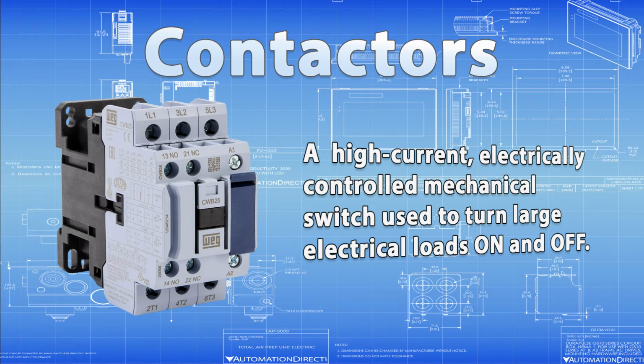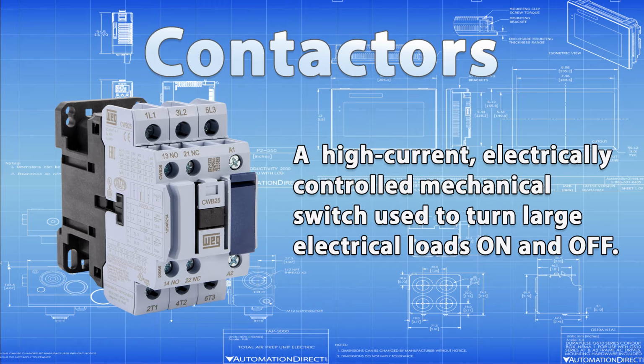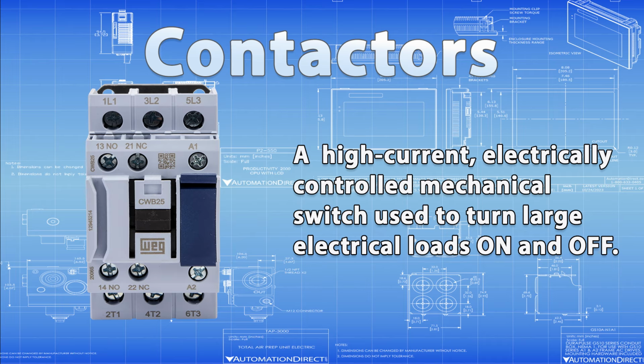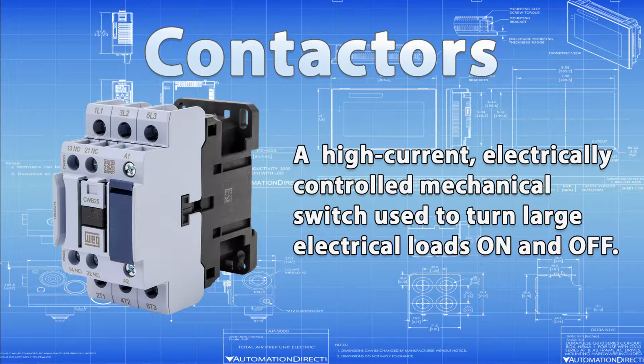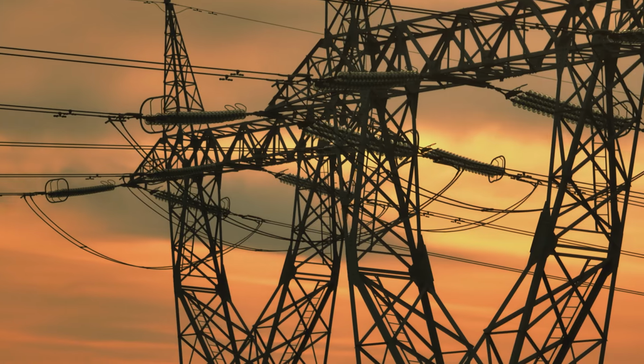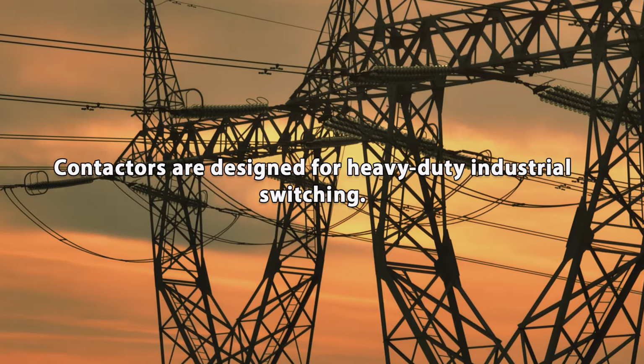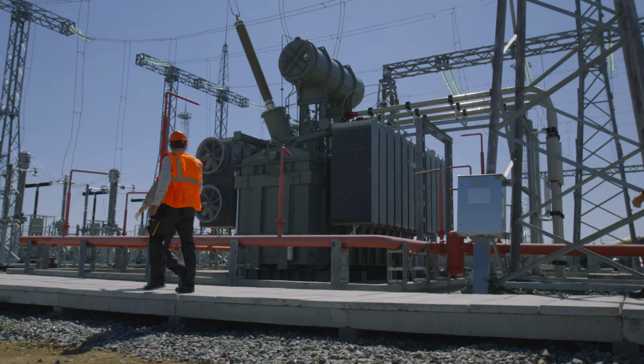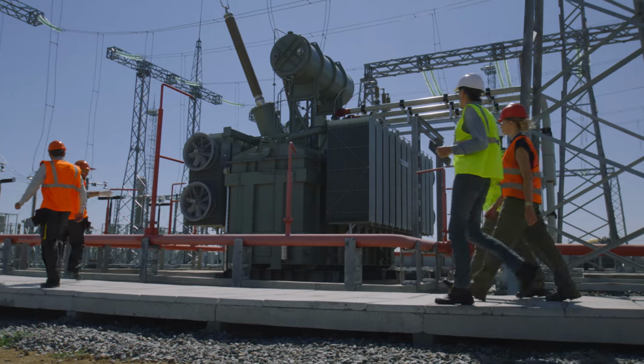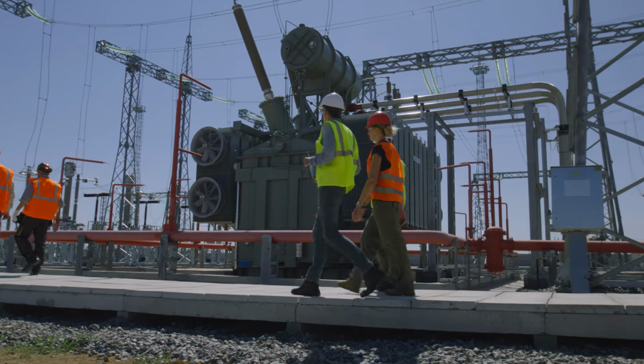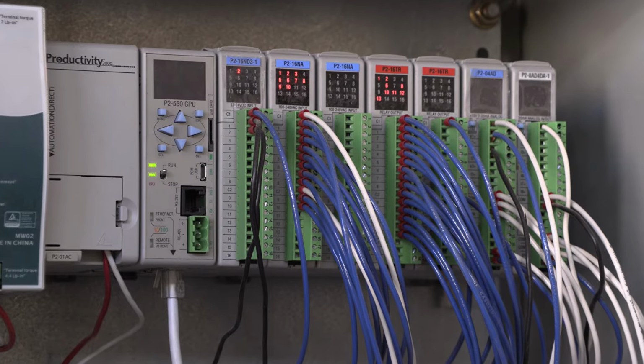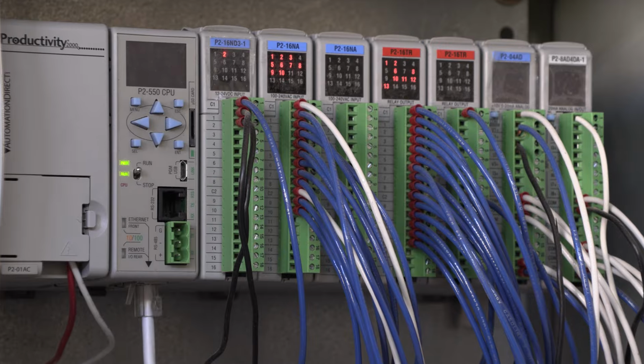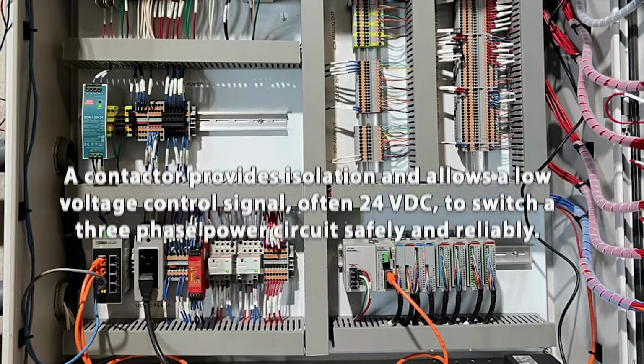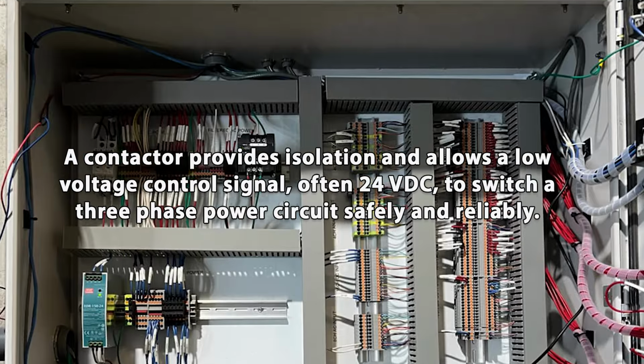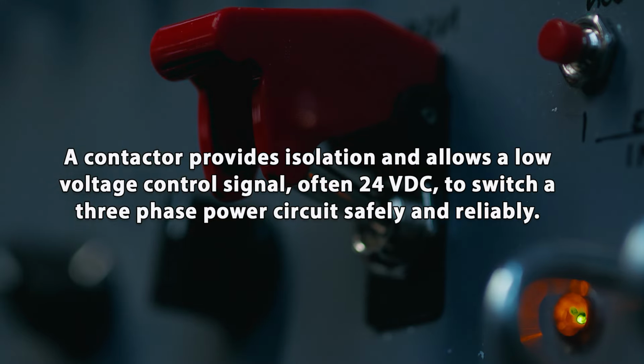A contactor is a high-current electrically controlled mechanical switch used to turn large electrical loads on and off. Unlike standard control relays, which are typically limited to 10 amps or less and often use solid-state internal components, contactors can handle hundreds of amps and are engineered specifically for heavy-duty industrial switching. Industrial motors, solenoids, and transformers generate large inductive electrical loads and voltage spikes. Connecting them directly to a PLC output would risk serious damage.